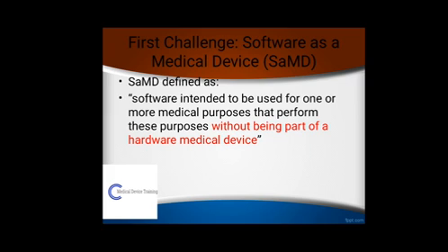According to the FDA regulatory, software as a medical device, SaMD, is defined as software intended to be used for one or more medical purposes that perform these purposes without being part of a hardware medical device. In other words, think of SaMD as software which on its own is a medical device. For instance, the software used to view images from an MRI on your phone would be SaMD. But the software that enables an MRI machine to run its tests wouldn't be. To be considered SaMD, software must not principally drive a hardware device.